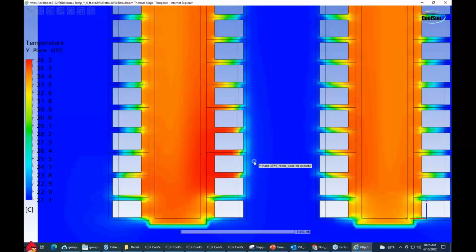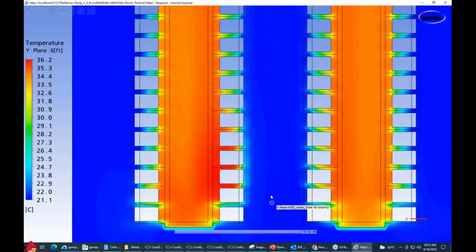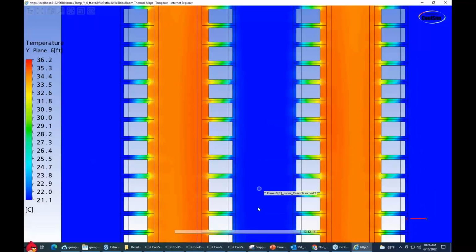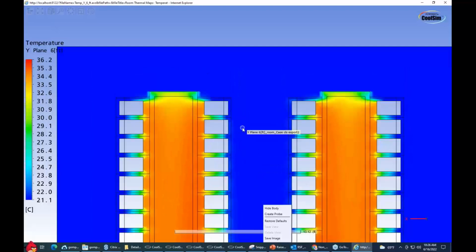And we're seeing some back pressure here that's causing the temperature to push, or the air to push through and leak into the inlets. And you notice it's more pronounced on this end. You see it leaking here and leaking here. This one in particular, the air is coming by, causing low pressure, causing leakage right along these rails. As we get to the other end, things look a little better, right? Down here I have less velocity.